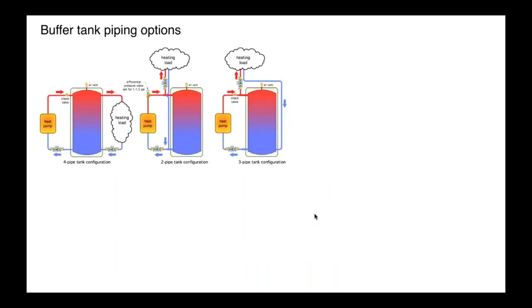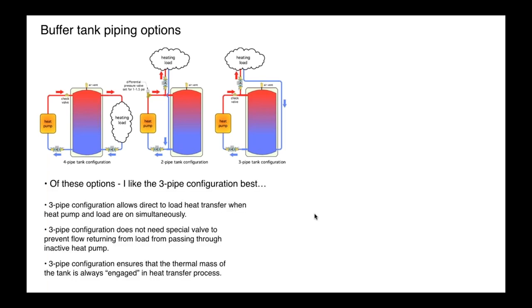Buffer tank options. Again, Hydronic 27, we get into it in more detail. There's different ways to pipe the buffer tank. I'm going to jump right to the bottom line here. I like the three pipe configuration. That would be this one over here. It allows what's called direct to load heat transfer. So if the heat pump is operating at the same time as the load, we can potentially send that flow directly to the load without having to first warm up the buffer tank. But it also routes the return flow back through the buffer tank. So we do engage the thermal mass of the buffer tank, at least on the cool side.